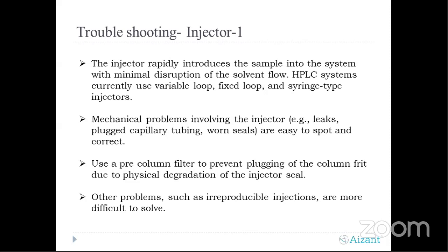So the third component is the injector, and you can see that the injector is a crucial part because it has to load the sample on the column. If any irregularity from the injector happens, it will create a lot of challenges. It will give a distorted peak. The reproducibility of injection will be lost, and the system suitability as per the methodology we can't achieve, and we can't run any analysis.